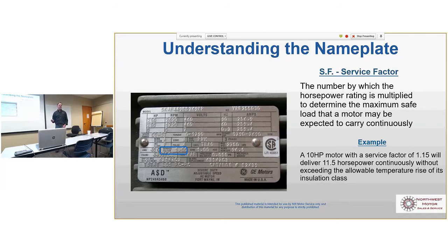I'll tell you, if you overload a motor 115%, unless it's one of these, you're not going to be overloading 115% for very long. Certainly not indefinitely. And even one of these, I wouldn't want you to do that very long. I mean, you really need to size the right motor for the right application. But these are designed to take the overload that most won't take.